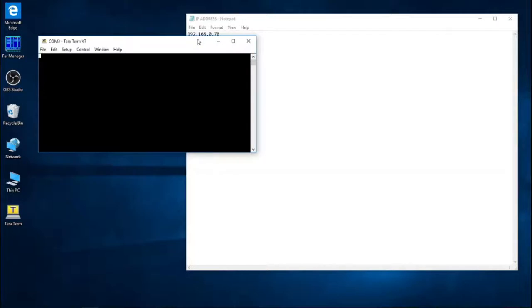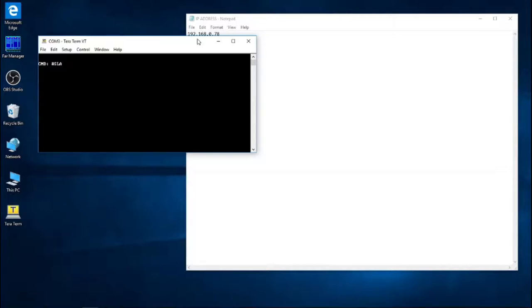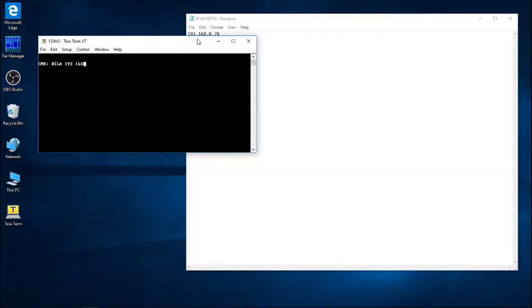New setting, and at this point we can send a command to the controller to change the IP address of that controller. To do that, you will be typing in the following. You'll be using the hashtag symbol, and then SLA, so SetLanAddress. Then you'll be typing in your new IP address for the controller. Instead of dots, you will just be using spaces. So it's 192 space 168 space 22 space 50.